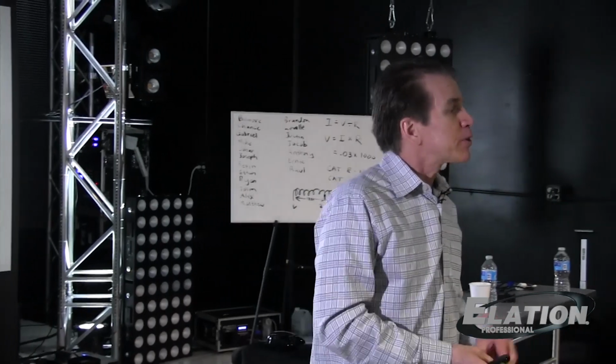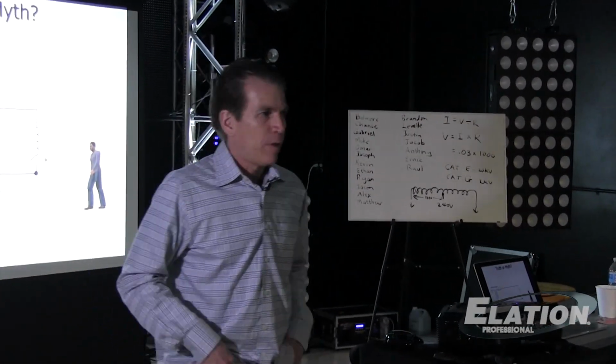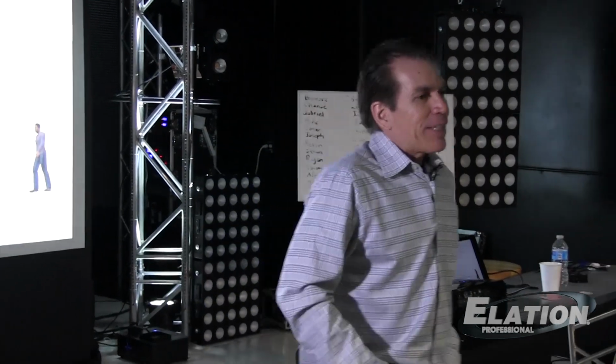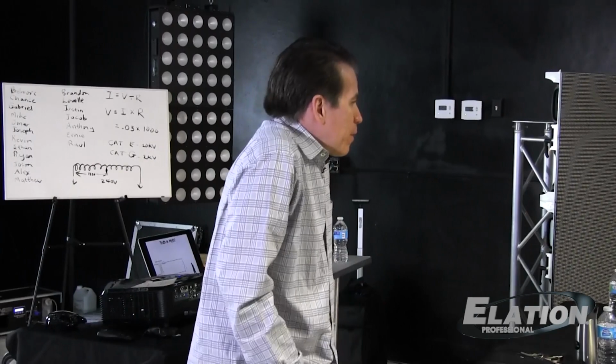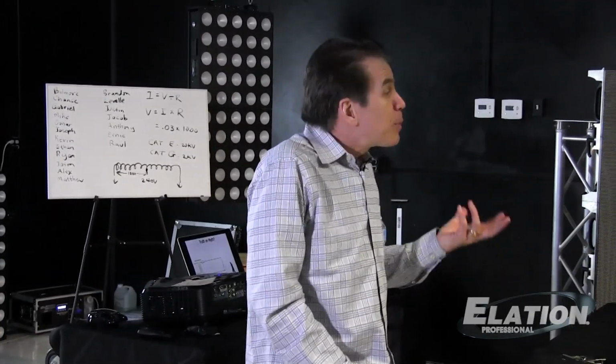And if you can isolate that piece of gear, then you can troubleshoot it and figure out what the problem is. I'll give you a perfect example. I was doing a workshop in New York City, and one of the people in the class had measured a high voltage, and I don't remember what the numbers were, but something that I would consider to be excessive between the neutral and the ground at the panel. I said, that's not right.